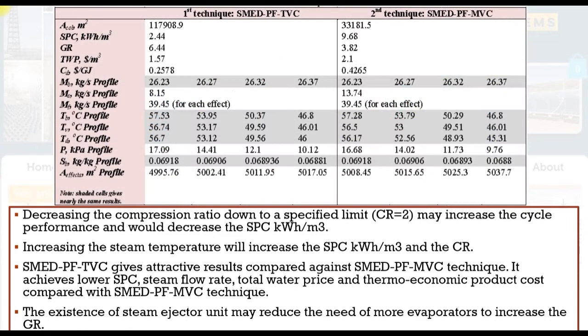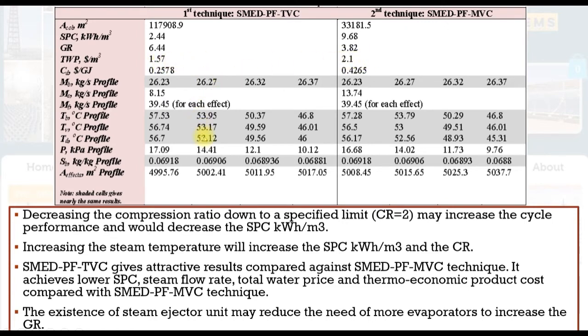Suppose we are going to compare against mechanical vapor compression. We have thermal vapor and mechanical vapor compression. For thermal vapor compression, total area of the solar field is increased. Specific power consumption is one-fourth: 2.4 against 9.6. The gain output ratio is 6.4 against 3.8, almost half. Total water price is 1.5 against 2.1. Therefore, thermal vapor compression is quite dominant.